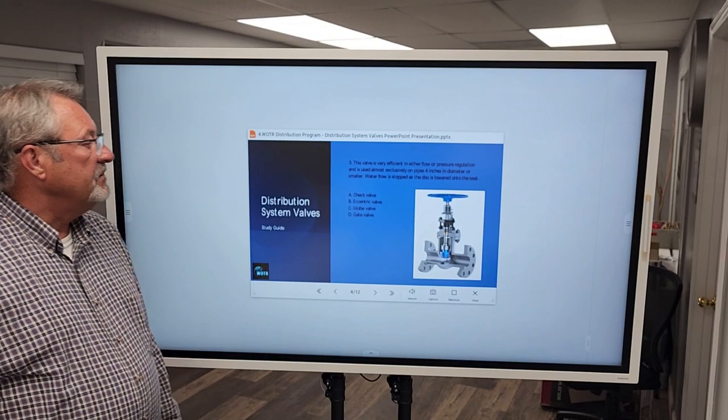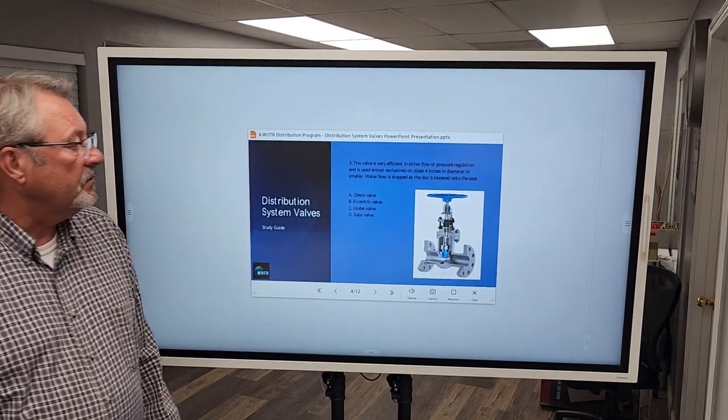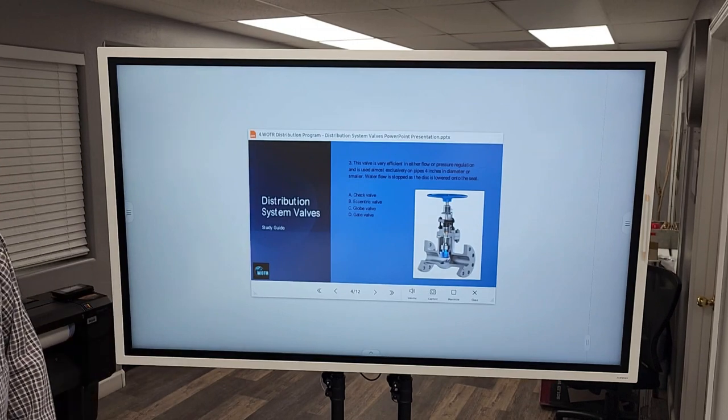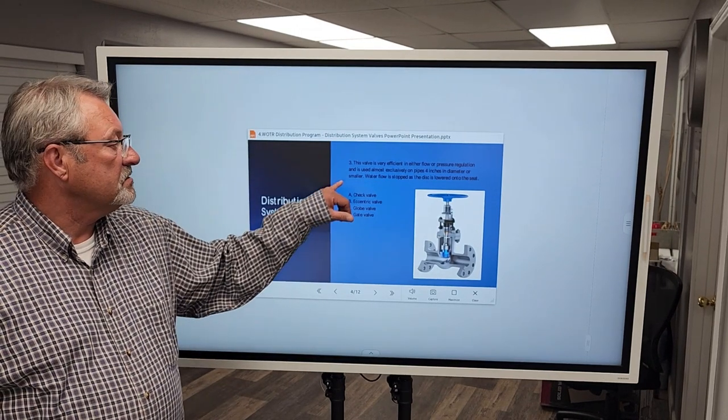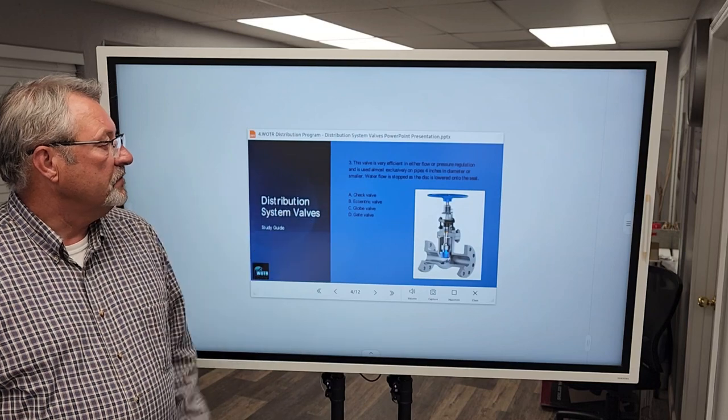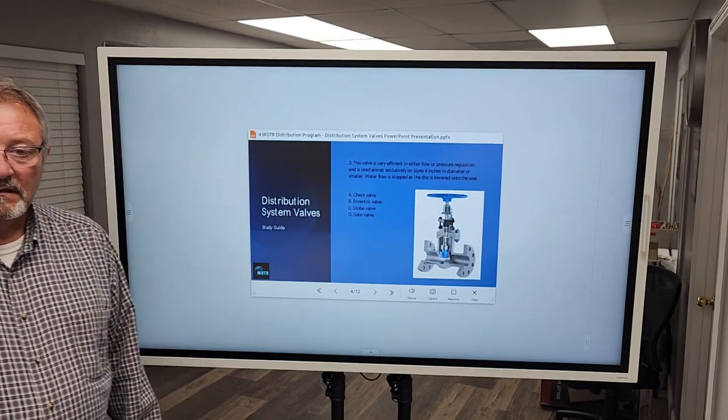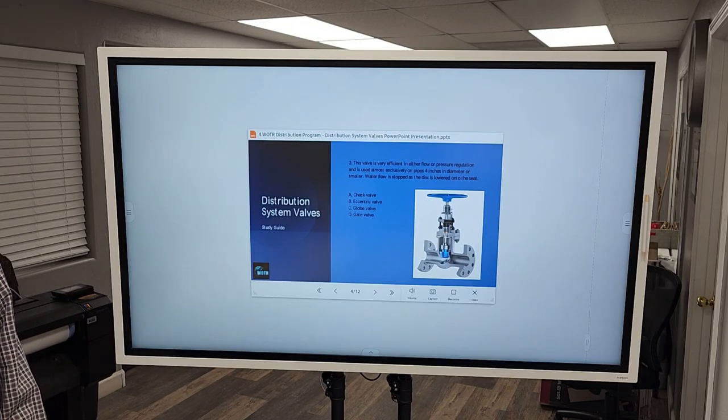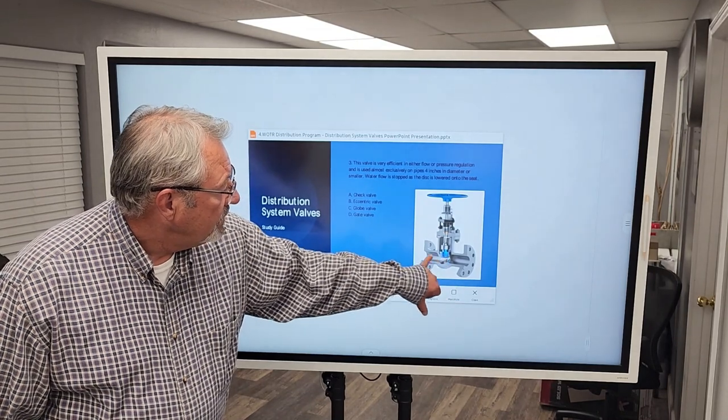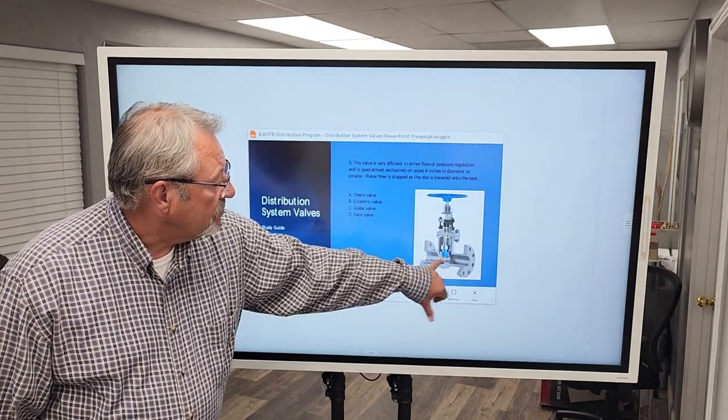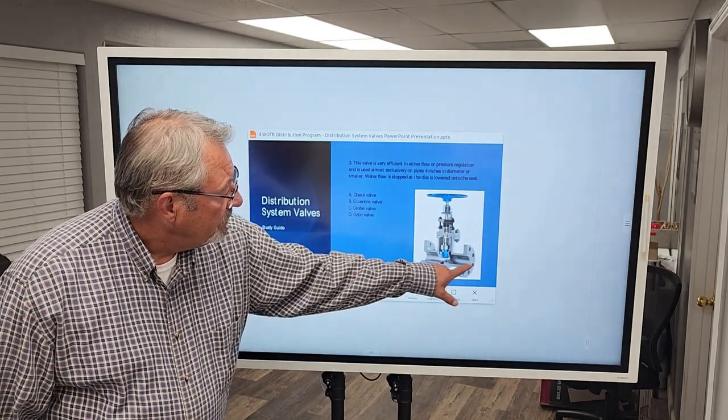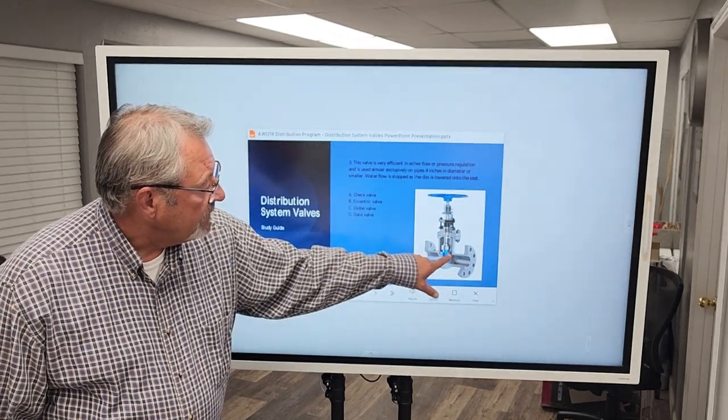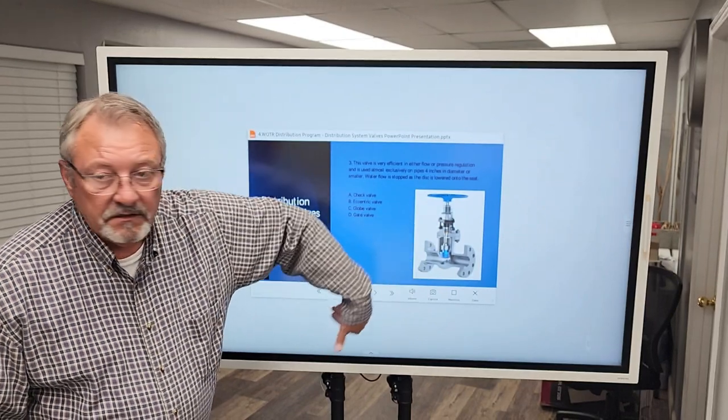Number three, this valve is very efficient in either flow or pressure regulation and is used almost exclusively on pipes four inches in diameter or smaller. Water flow is stopped as the disc is lowered onto the seat. Globe valve. You can see the closure element. They call that a globe. So as the water is flowing through, it has to flow through and that globe, if it's open, allows the water to continue on.